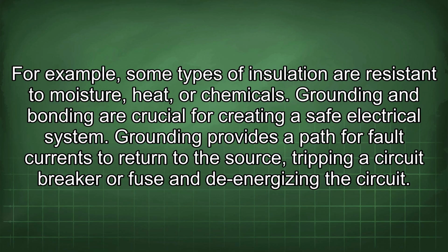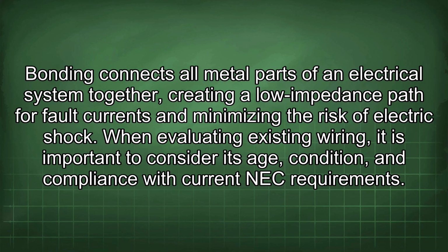Grounding and bonding are crucial for creating a safe electrical system. Grounding provides a path for fault currents to return to the source, tripping a circuit breaker or fuse and de-energizing the circuit. Bonding connects all metal parts of an electrical system together, creating a low impedance path for fault currents and minimizing the risk of electric shock.